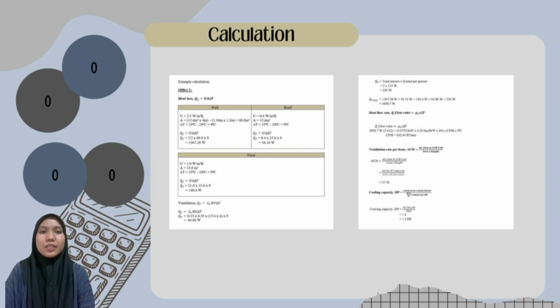Next, we proceed to the calculation. First of all, we need to calculate the heat loss for the wall, roof, floor, ventilation, and the occupants. After that, we need to calculate the total heat loss. For your information, the U value for each of them is different, using the standard required. Using the heat flow rate formula, we determine its CFM. Then, to calculate the ventilation rate per hour, or ACH, we use the formula airflow in CFM times 60 over the room volume, as shown in this slide.